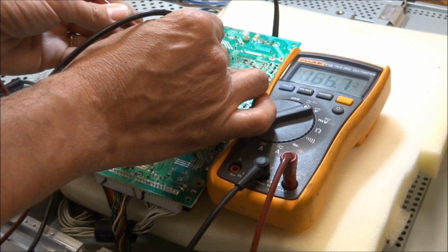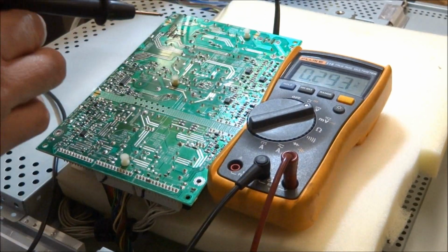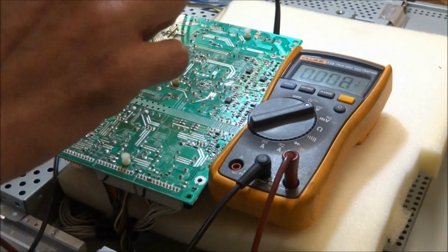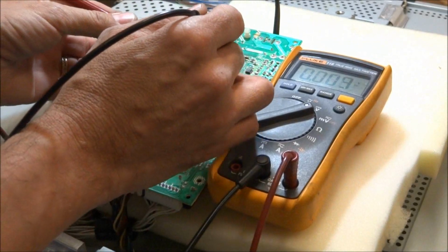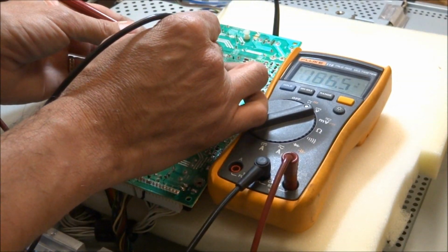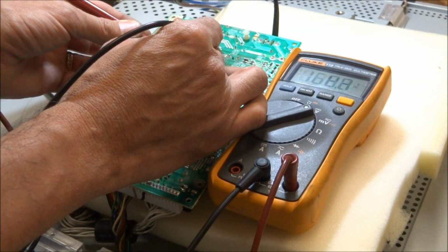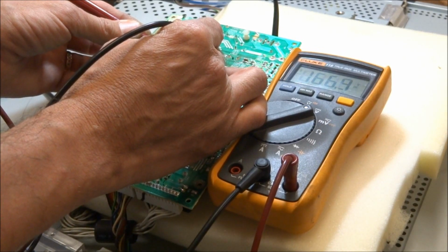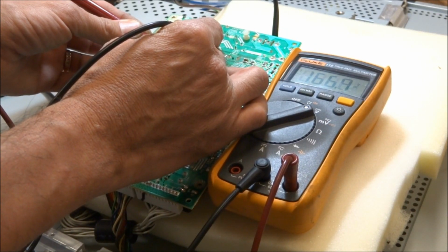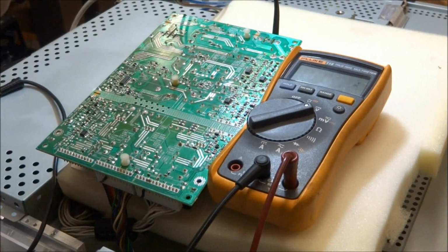I only see 166 volts, so let's go ahead and hit the power button. And we're still at 165 volts, so that's definitely a problem. I should be seeing, like I said, close to 350 to 400 volts, which is pretty much the average for a power factor correction circuit.